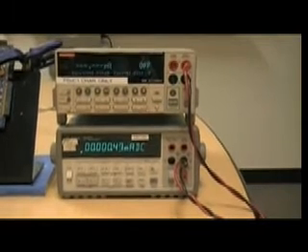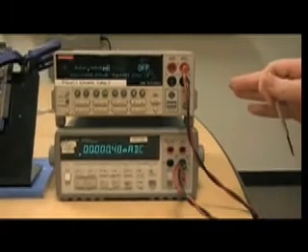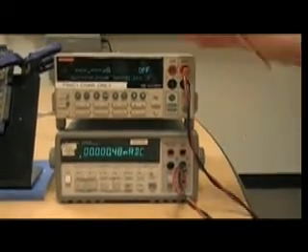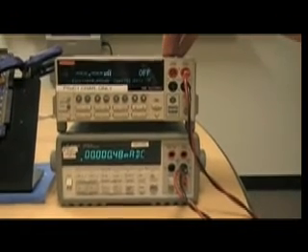So these are both recently calibrated and up to date. And what we're going to be doing is just showing a demonstration of what we'll be doing also on the PSOC, and we're just going to try to compare what this sinking capability is and what this is able to read.